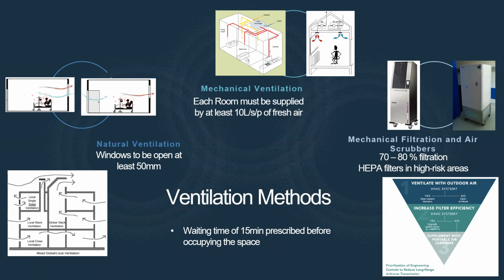That also talks into the positive and negative pressurization of that type of environment that you would like to operate at. If you have infection control, you would like to have a negative room, and typically you will actually get your 10 liters per second per person by means of extraction. In a burns or a neutropenic or hematology type setup or environment, it will be the opposite way around. You will extract in the passage and you will discharge fresh air at 10 liters per second per person into that room.